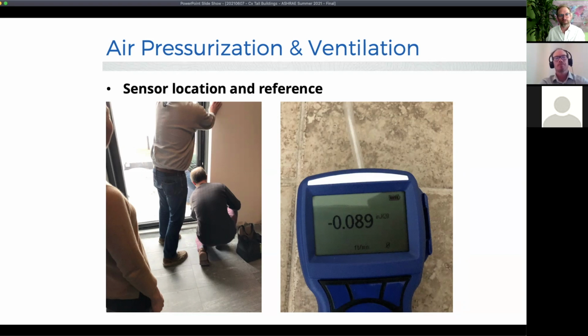What we find a lot of times is that the pressure sensors used to control makeup air or ventilation system units in residential buildings are looking at a reference between a hallway and a stairwell. Often they're not even looking to the right decimal place of pressure when working in IP units, so the control systems don't necessarily have control where we want it.